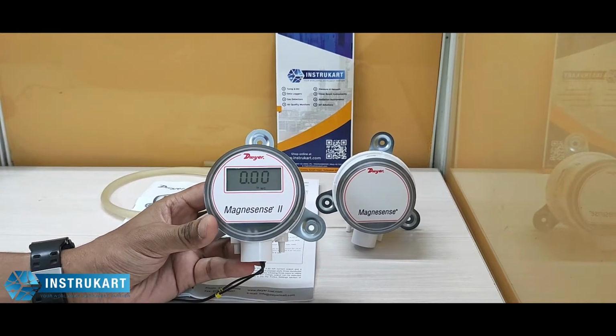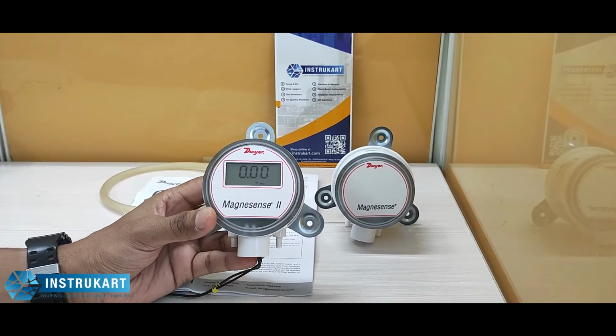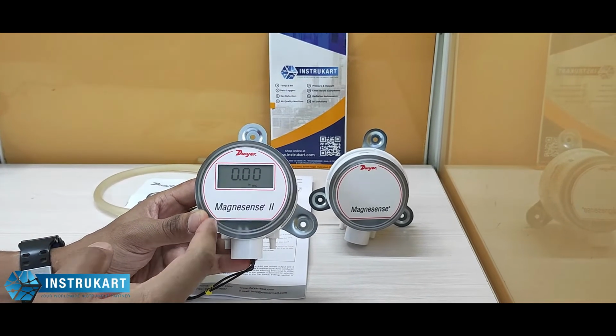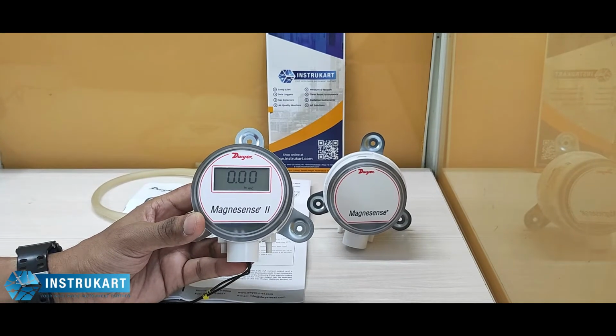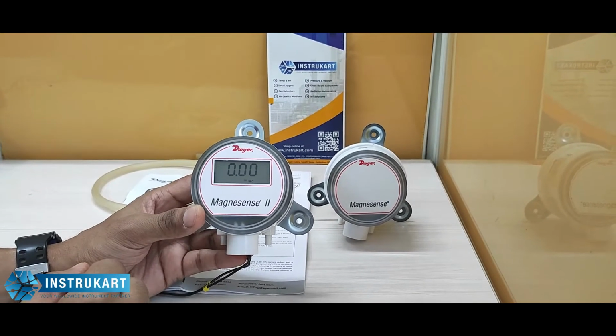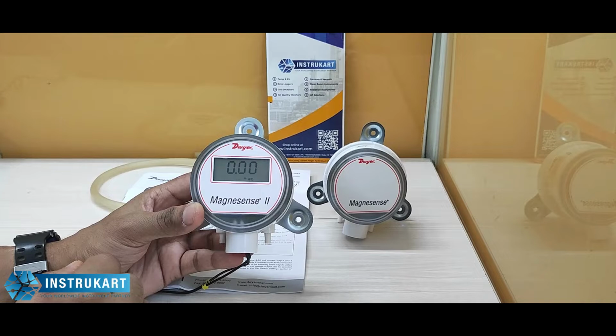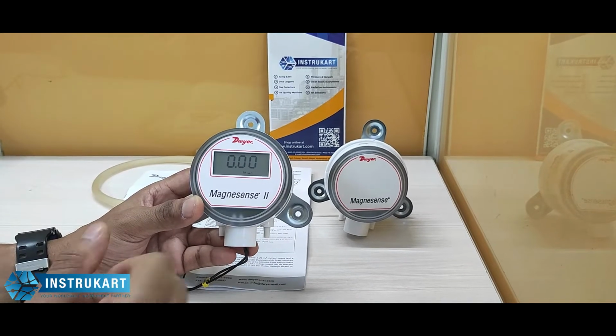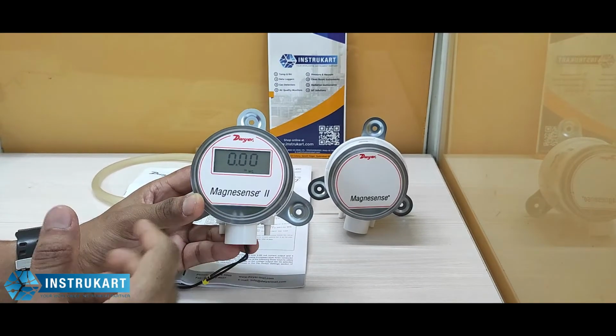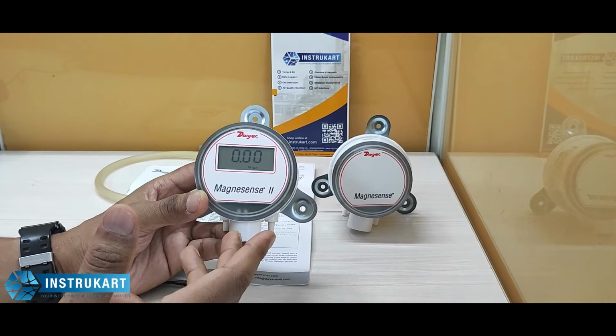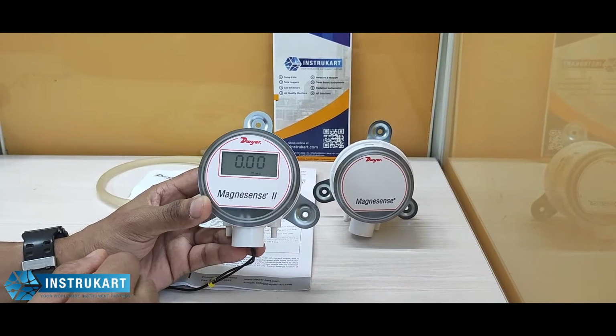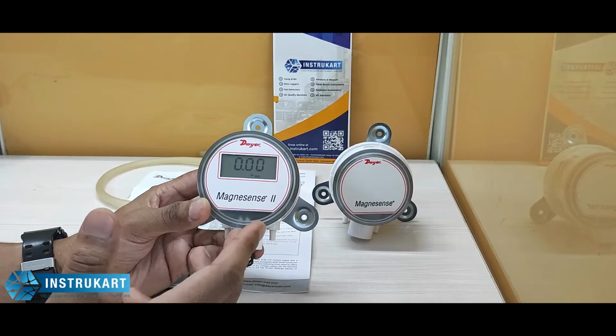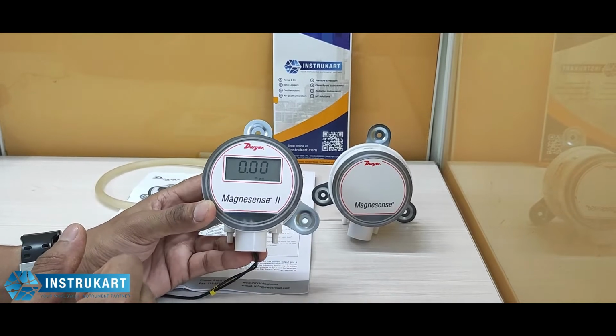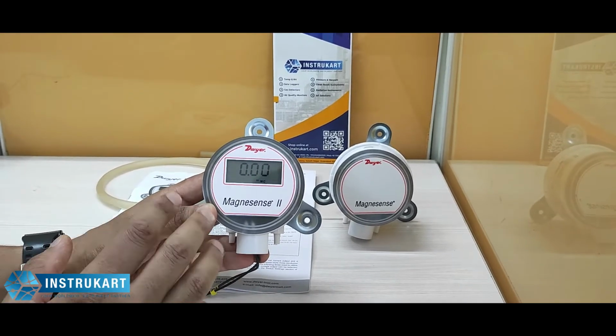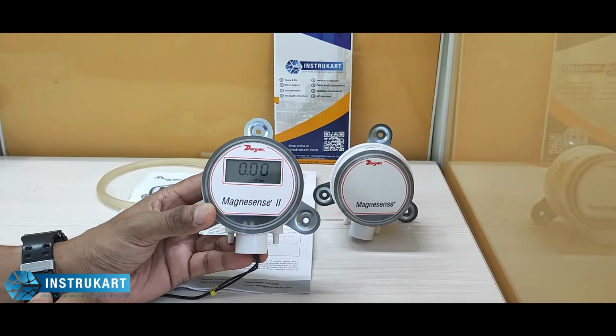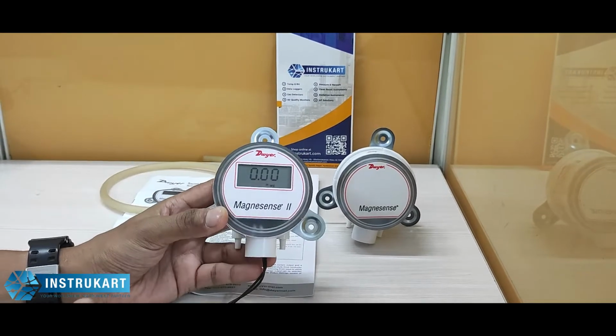We have got a differential pressure transmitter from Dwyer, and the series is the Magnesense series. This is a very popular series which is used in many HVAC units where differential pressure measurement is required, starting from clean rooms to laminar air cabinets to any kind of room to room, room to corridor differential pressure. You can use this device to check the differential pressure and transmit it with the output option.